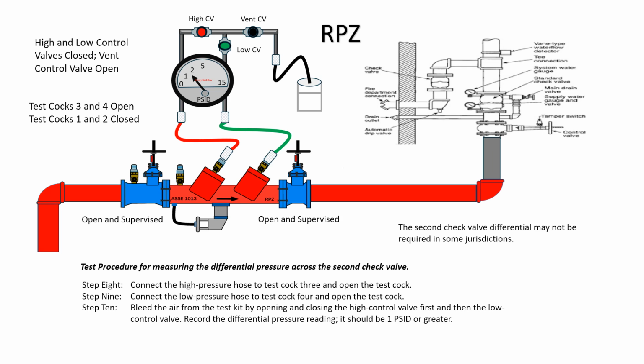Test procedure for measuring the differential pressure across the second check valve. RPZ. The second check valve differential may not be required in some jurisdictions. Step 8. Connect the high pressure hose to test cock 3 and open the test cock. Step 9. Connect the low pressure hose to test cock 4 and open the test cock. Step 10. Bleed the air from the test kit by opening and closing the high control valve first and then the low control valve. Record the differential pressure reading, it should be 1 psid or greater.